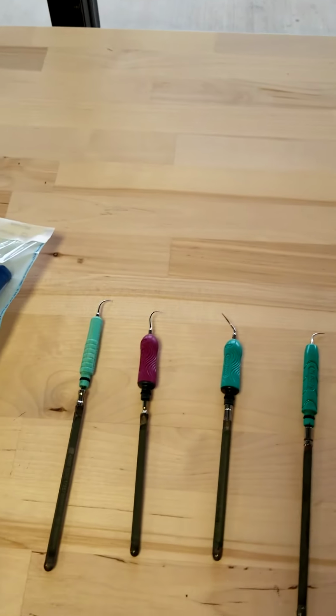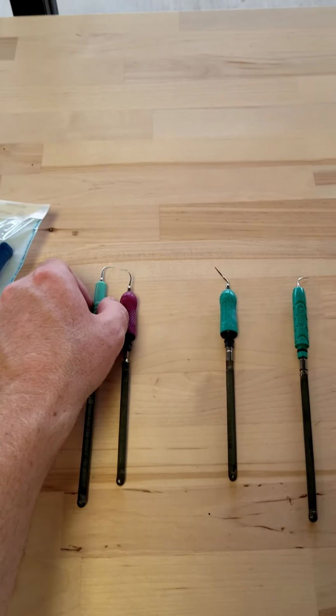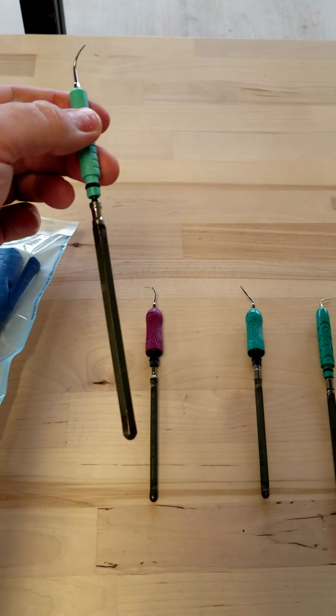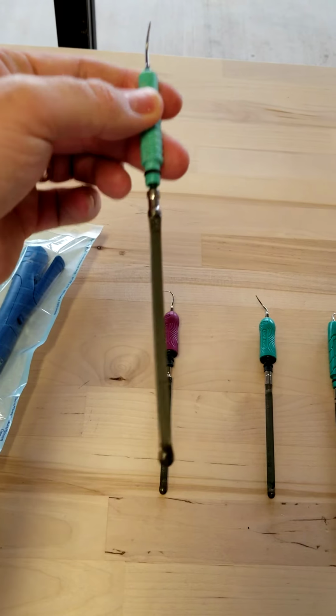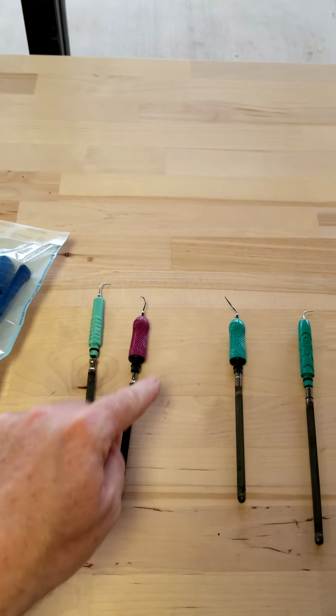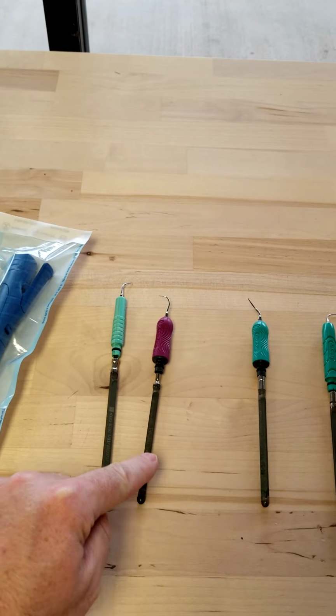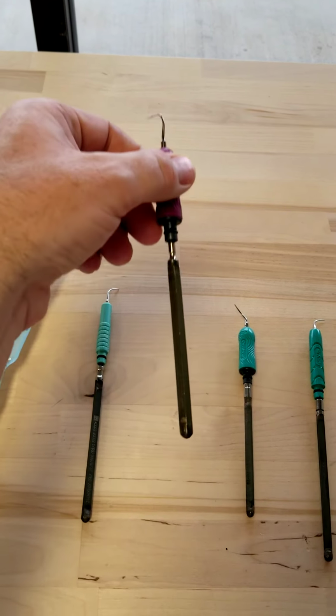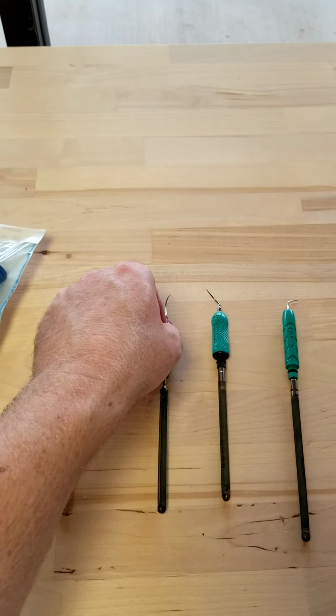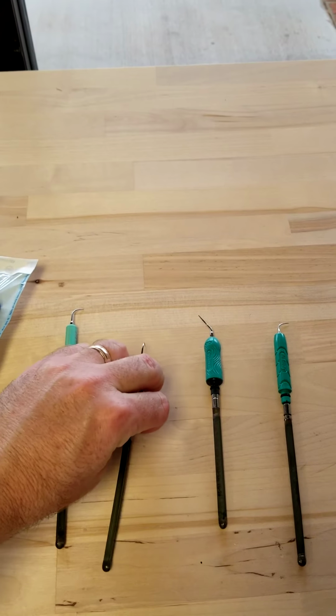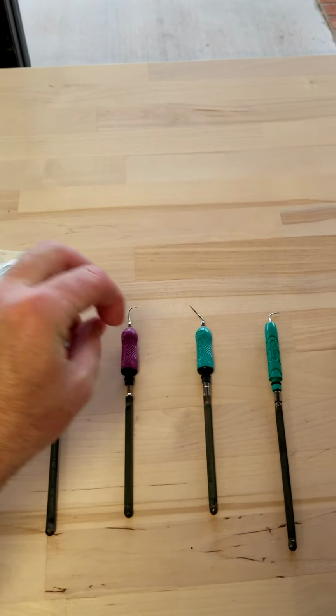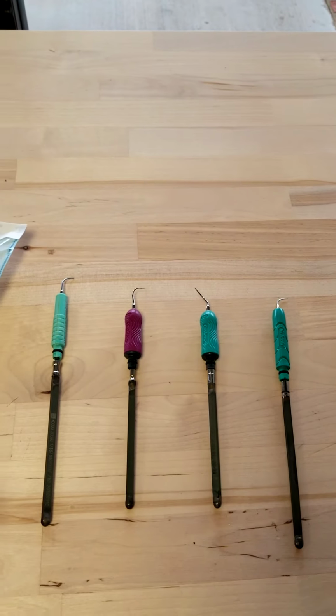One thing I did want to mention when handling these, there are a few rules. Number one, you don't ever want to stack these up to where this part of it gets bent, because the stacks on these, that's what they're called. This part here is the stack. If it gets bent, it reduces the effectiveness of these dramatically. So try not to bend them. If you drop these, it will break the tip off, and these are 160 bucks each on the low end. So just make sure you pay attention to that.